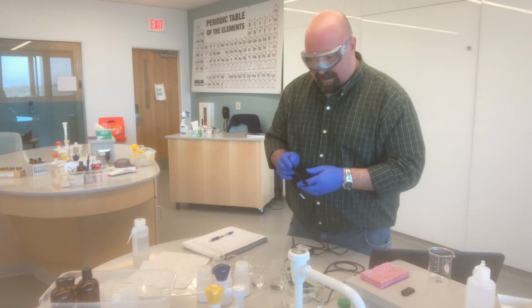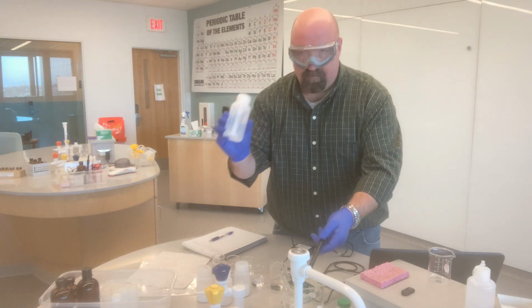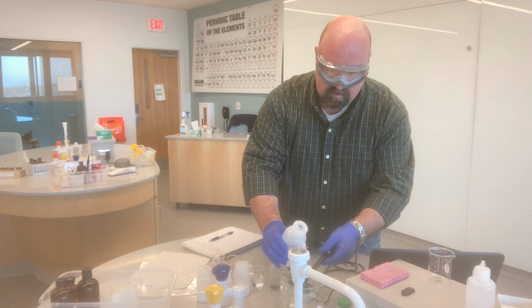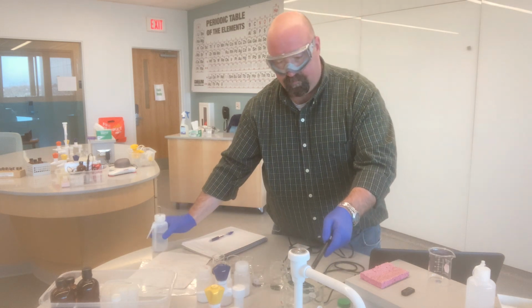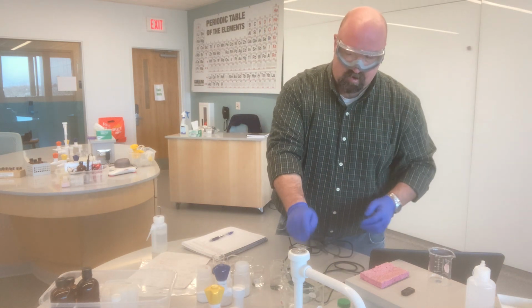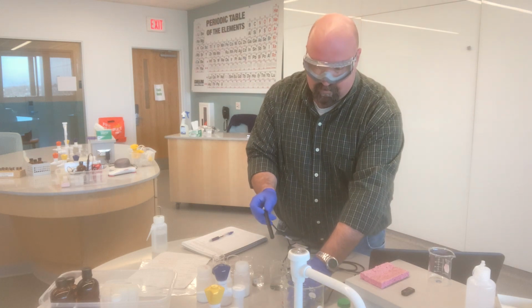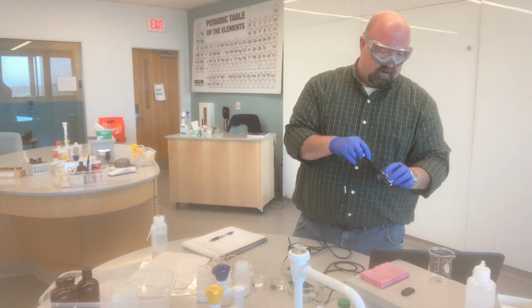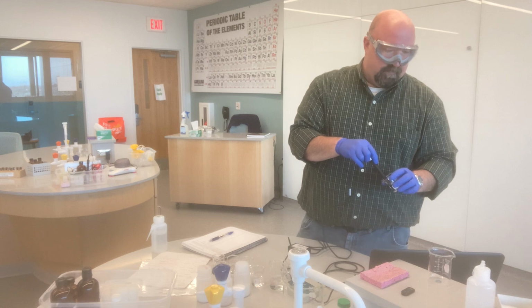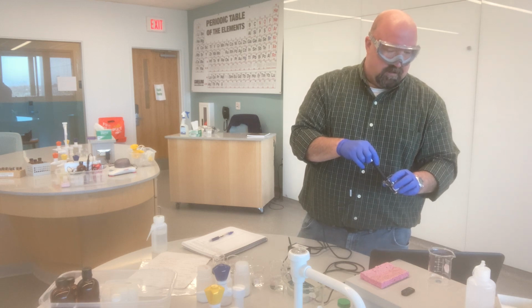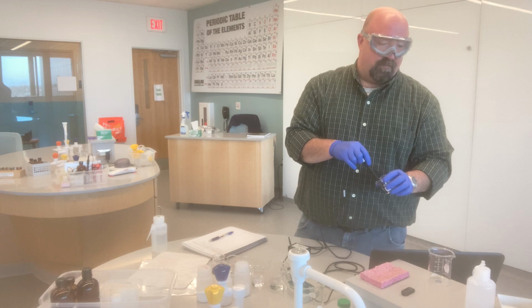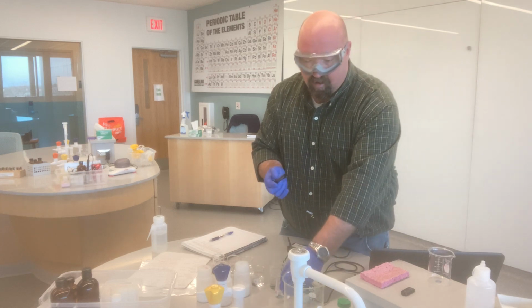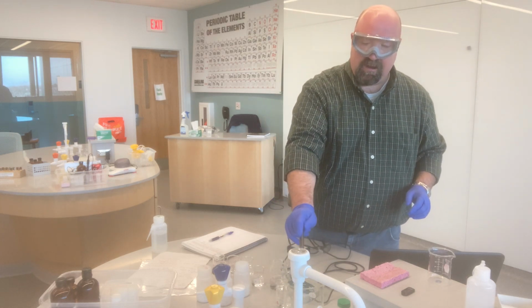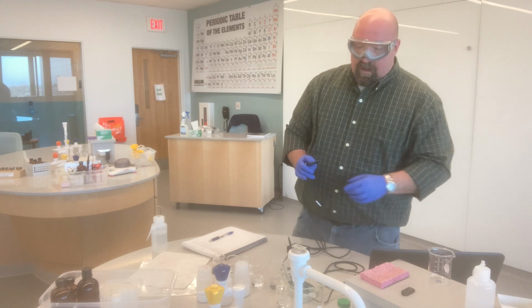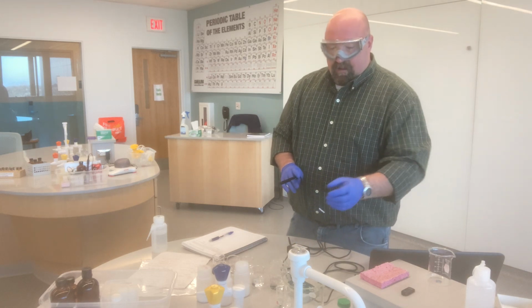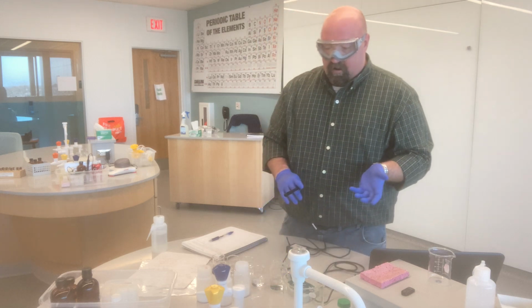Just to double check that even further though, I'm just going to rinse off the probe, use my squirt bottle, shake off any excess, then put it down into the distilled water to make sure that it is measuring that at 0. And it's measuring it at 4, actually, microsiemens per centimeter. Pretty much 0 when we're looking at our calibration range of 0 to 1000. And so now I'm ready to measure the conductivity of all my various samples that we prepared earlier.